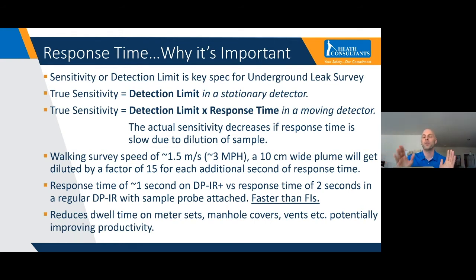So the big takeaway here, without getting too deep into the weeds, is that sensitivity can decrease if response time is slower. An improved response time can lead to a more sensitive instrument, that's really the point I'm making with this slide.